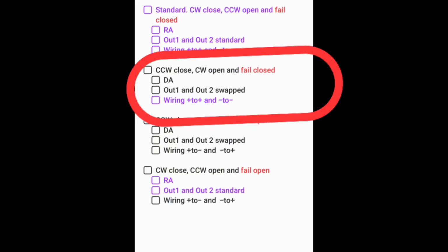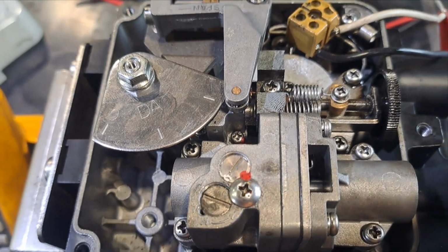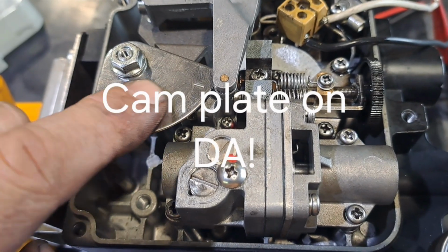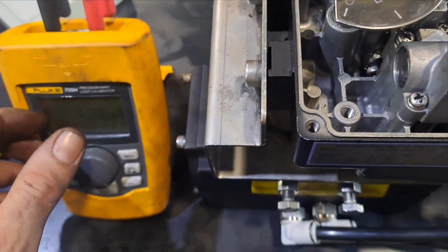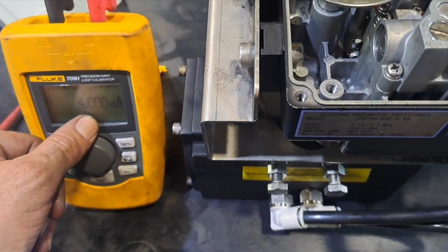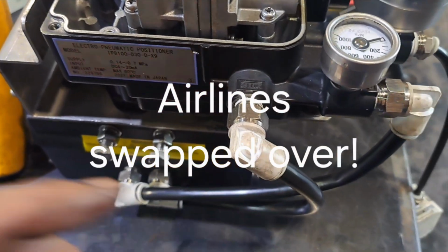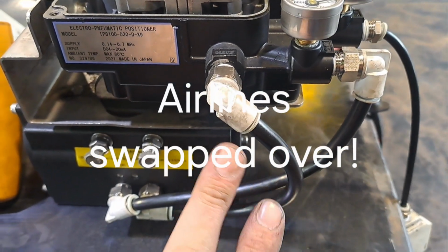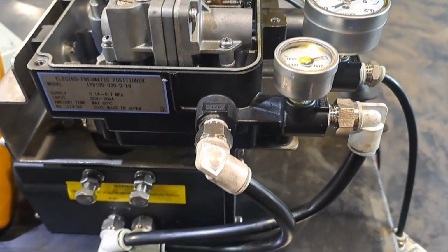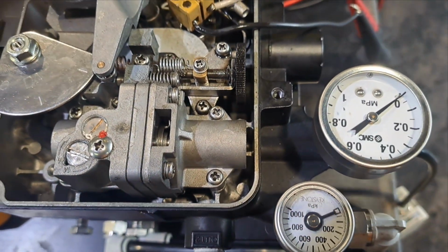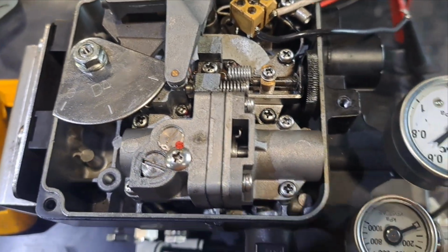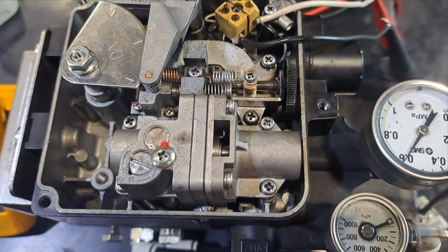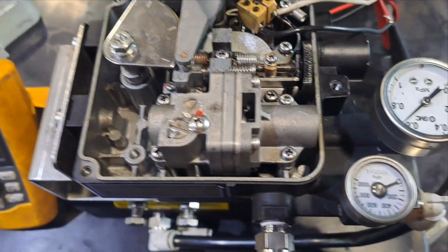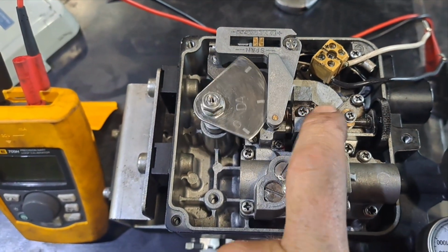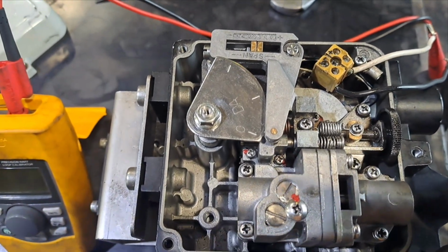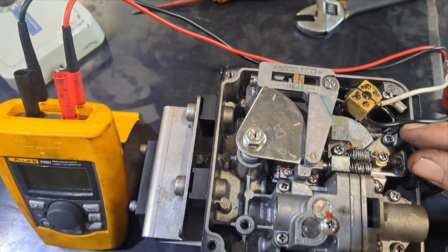For the next configuration, I've removed the indicator so we can see the cam plate easier. As you can see, I've turned the cam plate around and we are now on direct actuation. Let's see what happens with that. Just as a quick note, anytime you need to change the cam plate over from reverse acting to direct acting or vice versa, you have to swap the airlines over to match. With the cam plate turned over and the airline swapped over, I'm just toggling the counter lever to make sure that everything works fine.